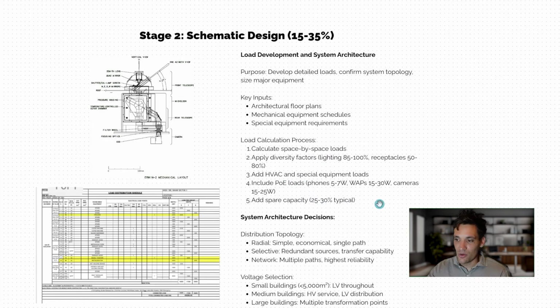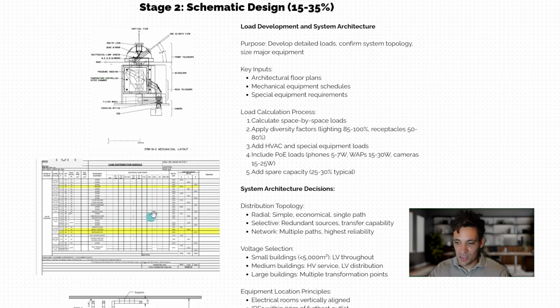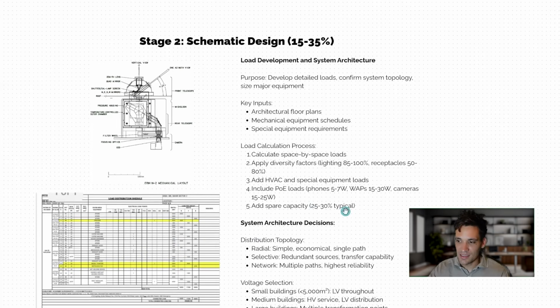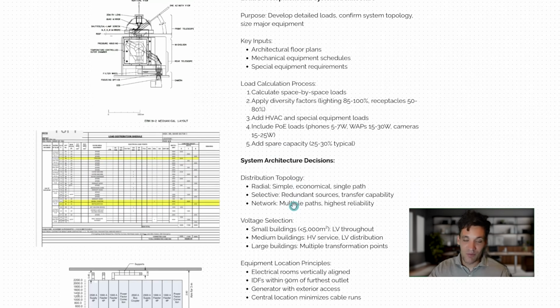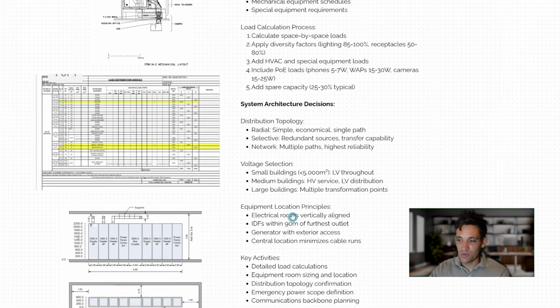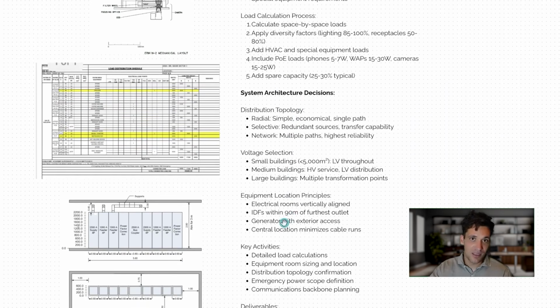Then we're going to go through and calculate all the loads for the system. We're going to create a register of all the loads connected to the system. Primarily, we want to focus on any of the big loads and take into account their demand factors. Typically we get that from standard documentation, or maybe there'll be relevant standards that tell you what load factors to consider for lighting, lifts, pumps, and so on and so forth.